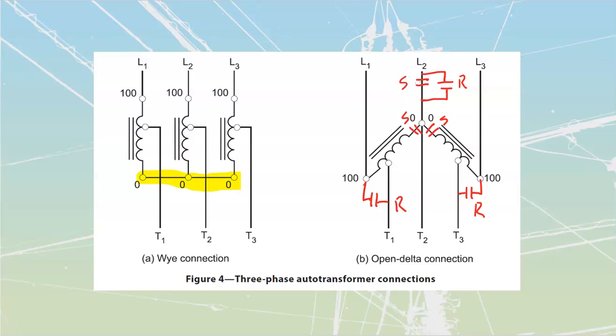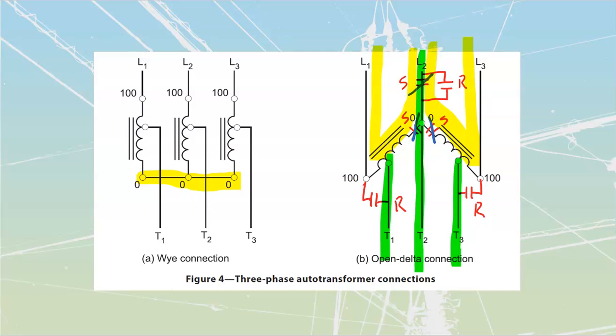So if I were to go through my sequence, I'm not going to go through the timing sequence, but at the instant of startup, I would have closure on all of the S's here, which would mean that I would be able to flow line current through like that, and line current through like that. And when that happens, that's going to energize these over here, which would mean that I would also be able to take off current coming through here on the 80% tap. Take off current over here on the 80% and take off over here. The actual delta that my motor is operating over top of is circumscribed by that triangle that we are going to have over there.